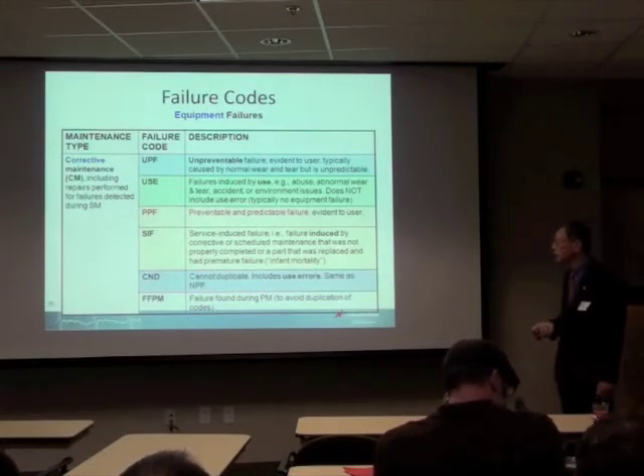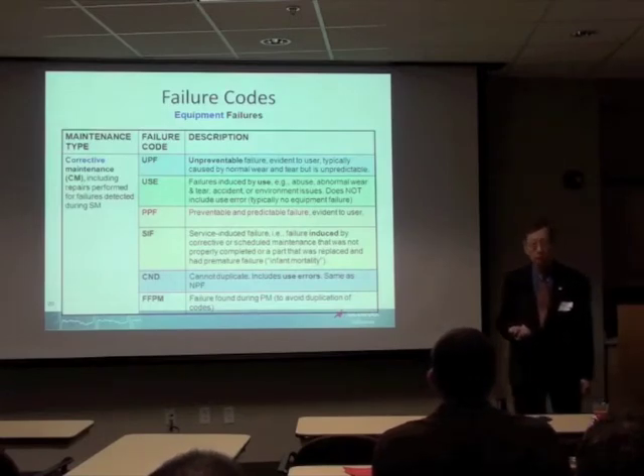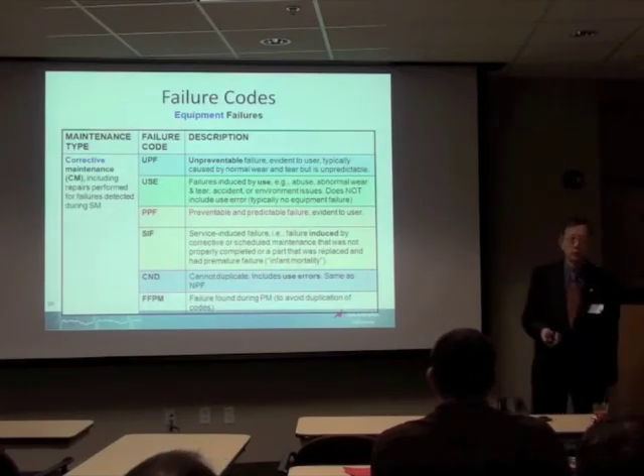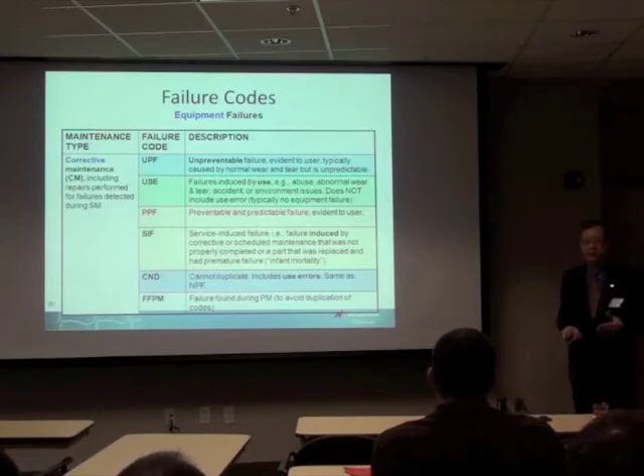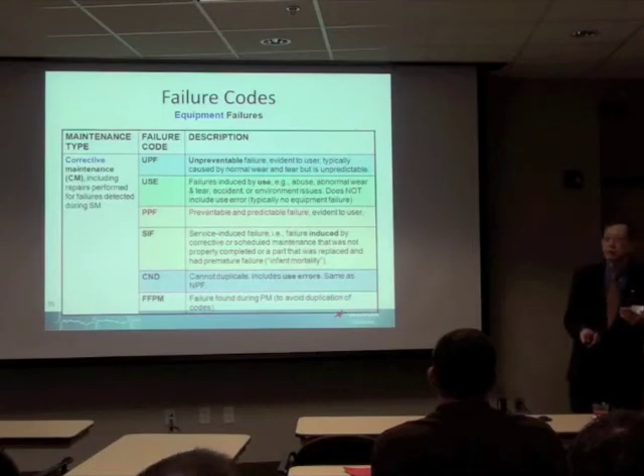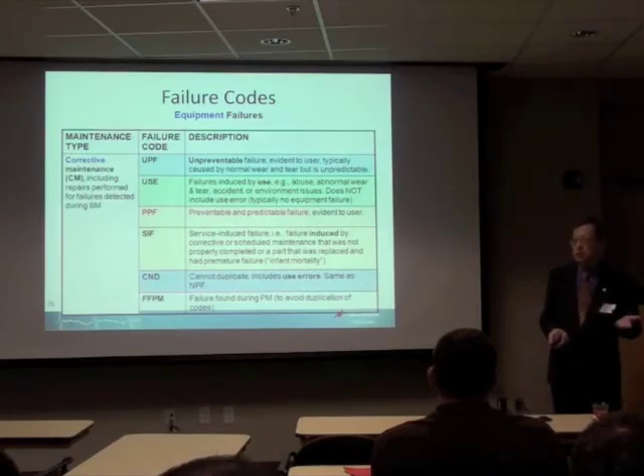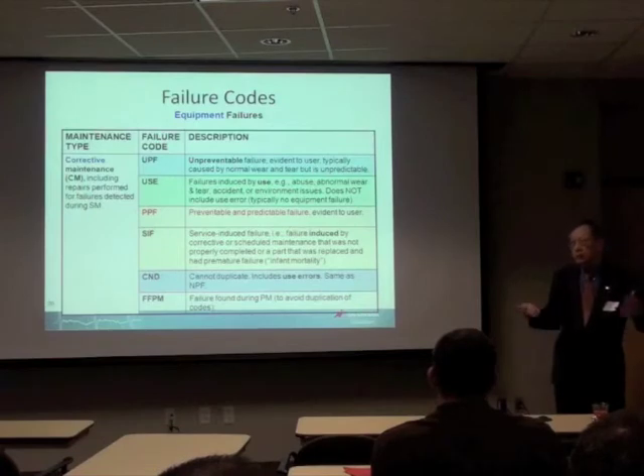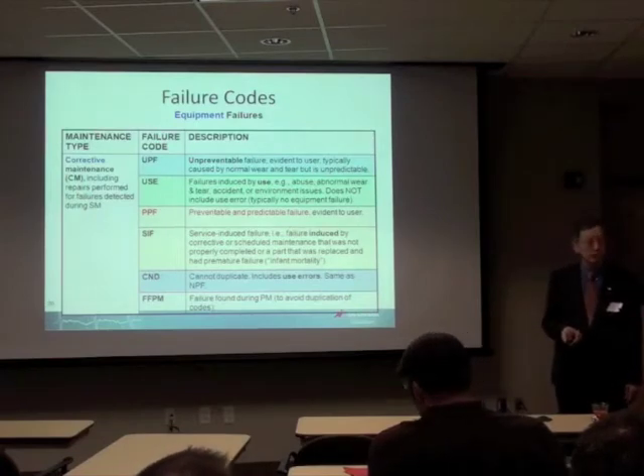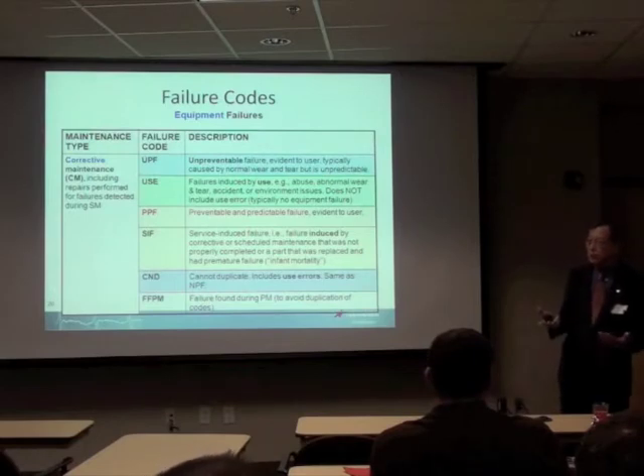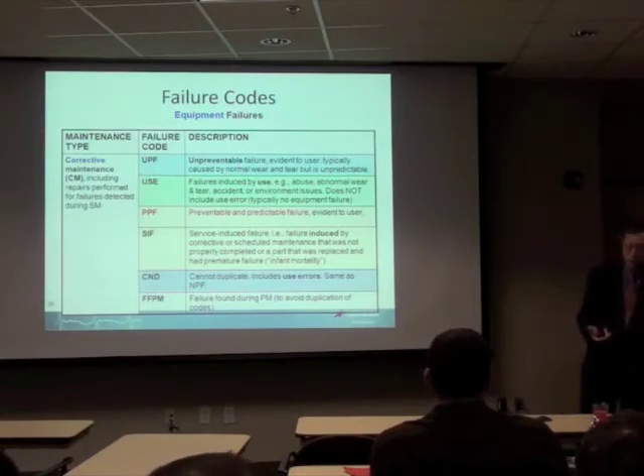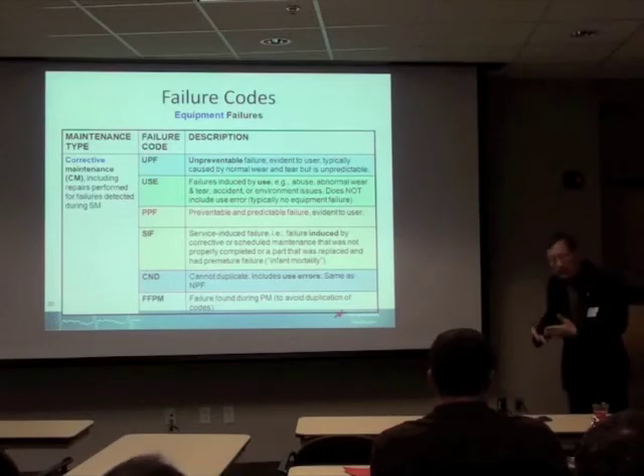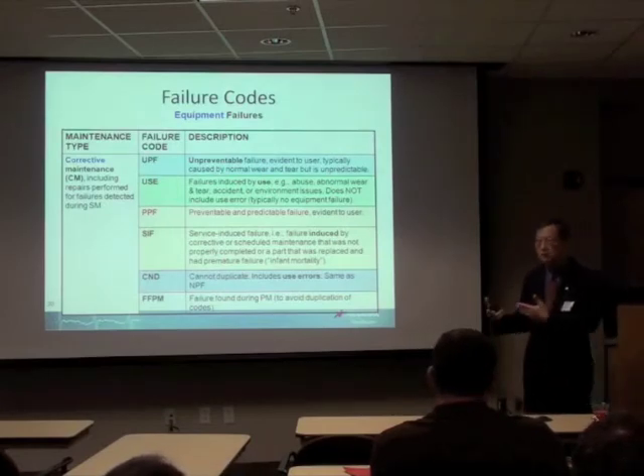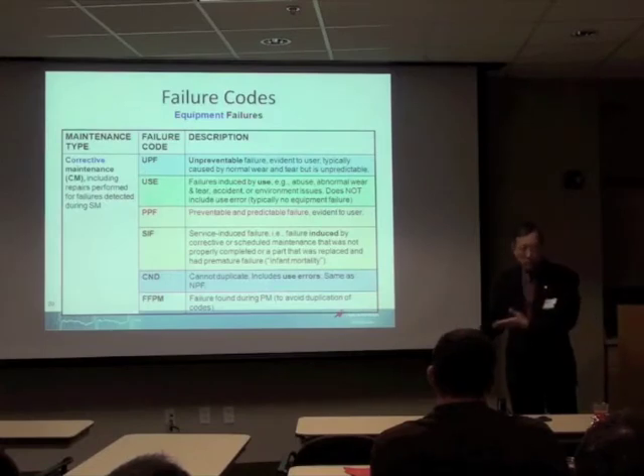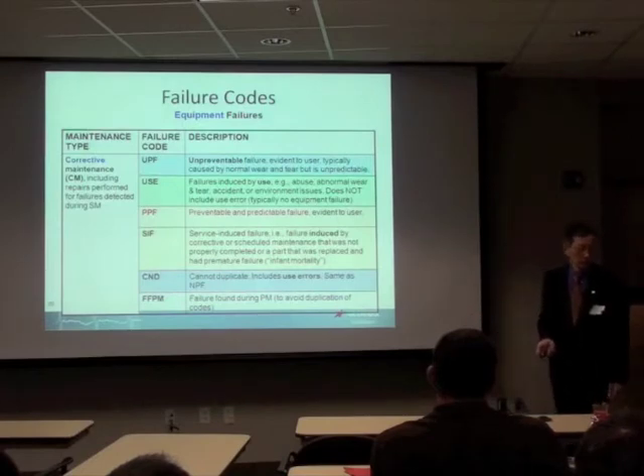One notable example of this is a well-known manufacturer of sterilizers - I guess you know the name. They did a study. They have a standard recommendation of replacing a certain valve in one of their machines 4 times a year. These days they decided to try replacing it only 3 times a year instead of 4. To their surprise, the reliability, the uptime, was higher with fewer replacements, because that valve is notorious for having a lot of infant mortality problems. So you put it in, and it's very likely that in less than 4 weeks it will fail.